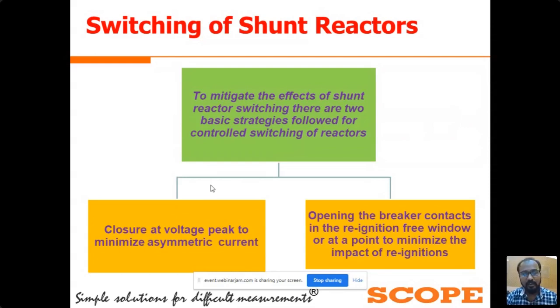But at the opening of shunt reactor, we have the reference of system voltage and the system current also. So for the opening of shunt reactor, we can take the reference angles of the current and the reference of voltage also.